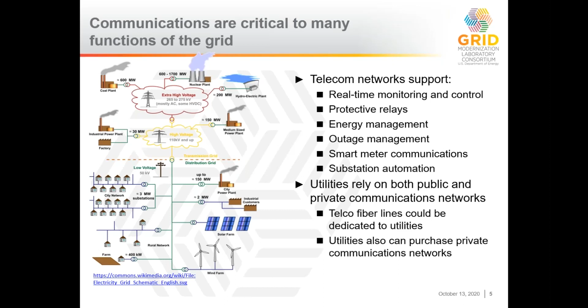We originally wanted to use fiber optic, as we were going to pull a new AT&T line out to the substation. The cost of that ended up being significant because it was a rural substation. So we ended up running with a 4G modem, but placing data analytics at the device so that we could compress and send the data in a way that doesn't just block its own communications. Because essentially, if you think of it as a pipe, at some point you can block that pipe by just sending too much information through it. So, next slide.